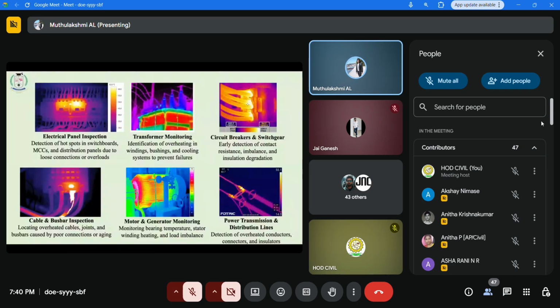Let me explain one image: in electrical panel inspection, the outer area shows purple and blue, with purple indicating the coolest part, while orange and white patches in yellow indicate the hottest area. This gives information about thermal pattern distribution, helping interpret the major causes of temperature deviation - loose connections or overloading could be causing the highest temperatures found during panel inspection.